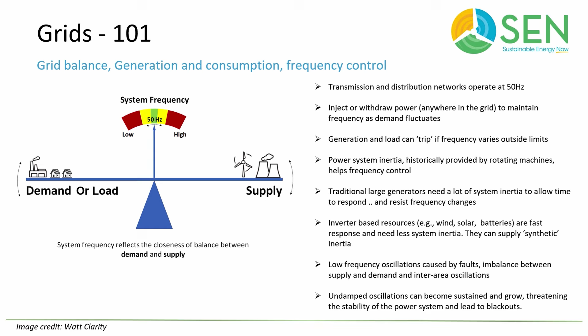So, quickly looking at how we protect the grid. They're very dynamic environments and have to be robust to manage a large operating envelope. Faults can arise from a number of different sources, as noted on the slide. So what we need to do is to be able to quickly and effectively distinguish between normal operations, including operating at the upper limits of equipment rated capacity, and fault conditions. And this is the job of protection relays: they need to be quick, accurate, reliable, selective, and stable throughout their operating envelope. One particular signature of a fault is high fault current, which traditionally large thermal generators can produce. There are other ways of detecting fault conditions, such as distance relays and differential current, etc.